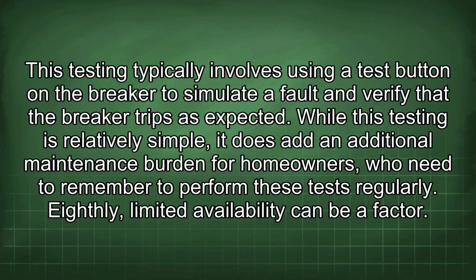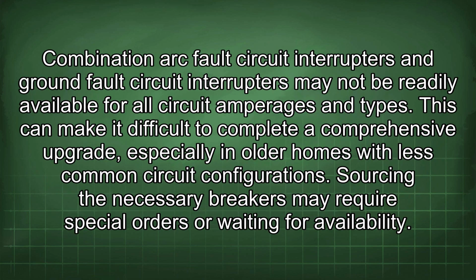Eighthly, limited availability can be a factor. Combination arc fault circuit interrupters and ground fault circuit interrupters may not be readily available for all circuit amperages and types. This can make it difficult to complete a comprehensive upgrade, especially in older homes with less common circuit configurations. Sourcing the necessary breakers may require special orders or waiting for availability.